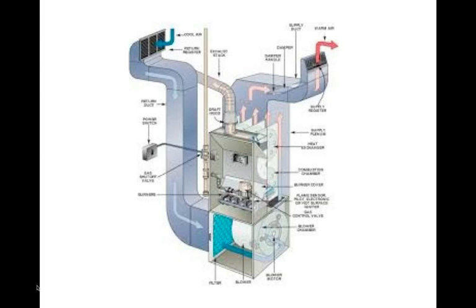For a home unit, you have a vertical unit with a gas heating device and a heat exchanger. You blow air through the heat exchanger so you don't mix it with the burning gases, it goes up into the house, comes back down through a duct on the wall, and is recirculated. Notice that many home heating units don't have a fresh air intake — the flexible metal duct at the top is an exhaust for combustion gases from the burner, not a fresh air intake.